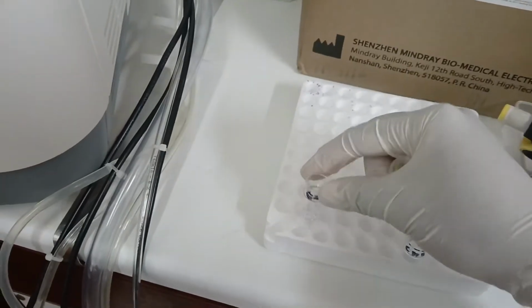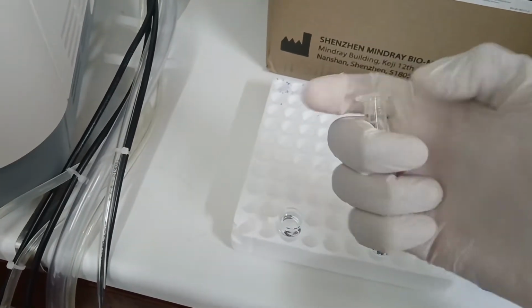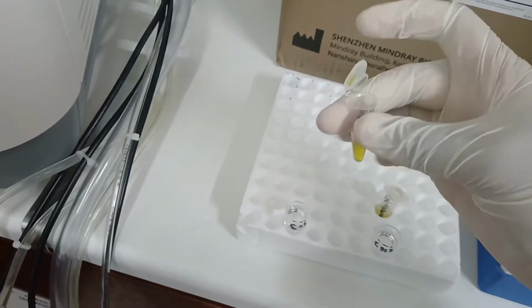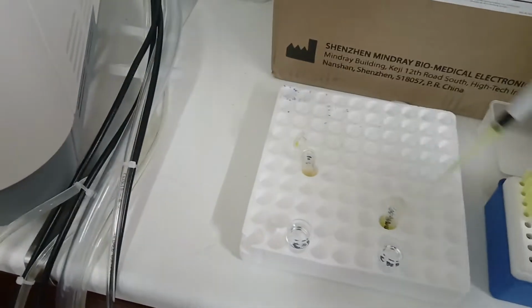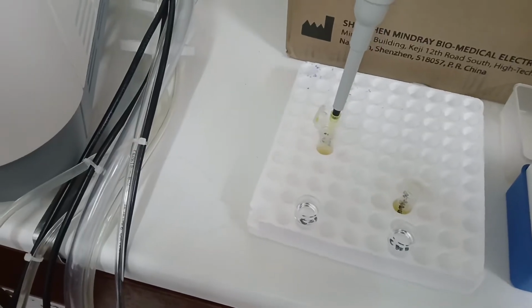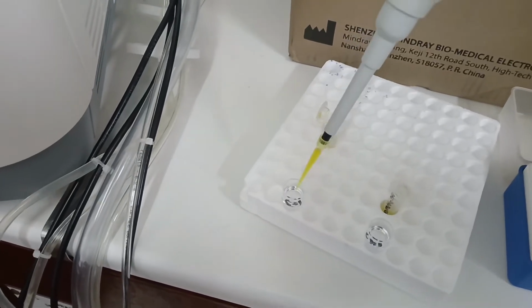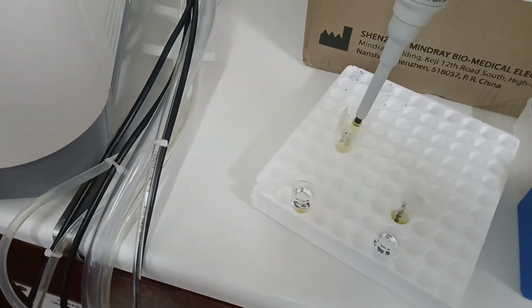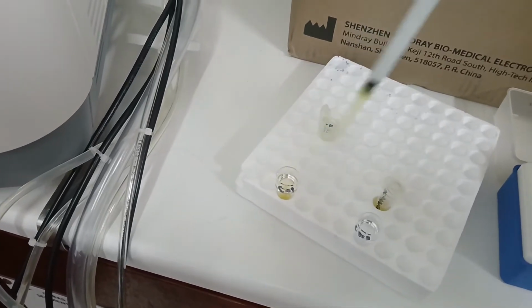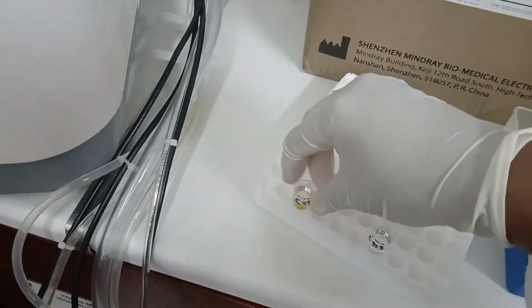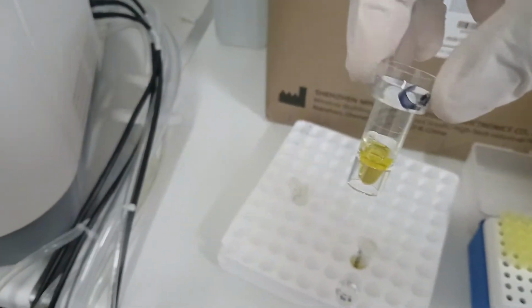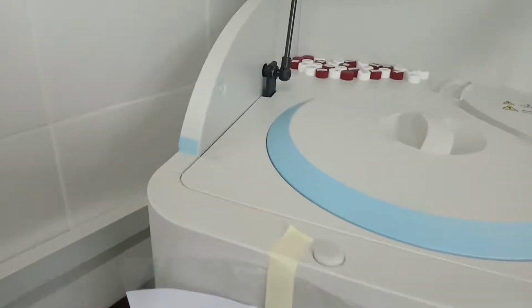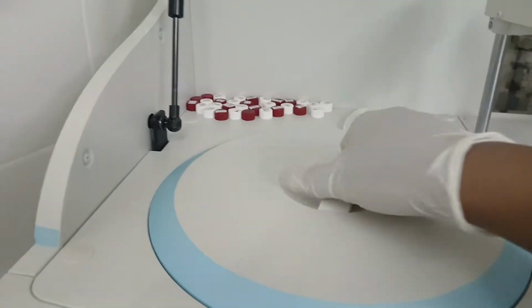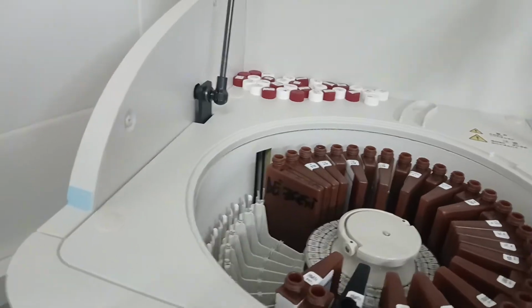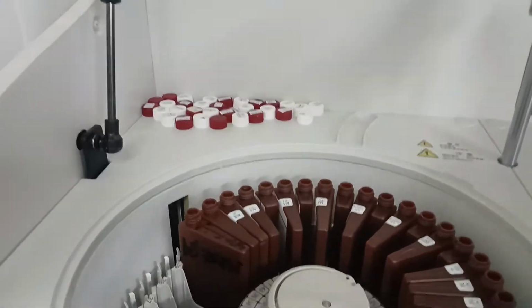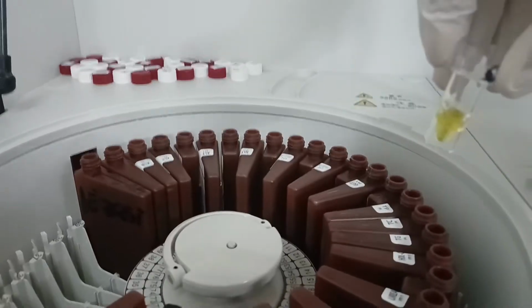That's our microtube. It's labeled as the cal. And so we'll open our calibrator. It's a multi-level calibrator, as I already mentioned, and then we'll transfer an amount into our microtube. Now, anything above 300 microliters will be fine. In fact, the machine will even use less than that. And so this quantity is enough, and then we'll transfer to our machine. So we'll open the machine, and then we'll put our calibrator in there. We'll load it. So that's our calibrator.